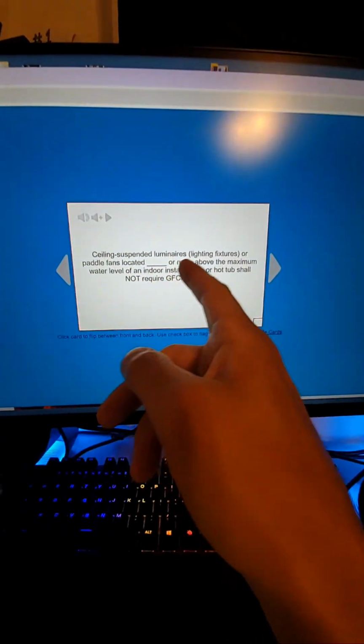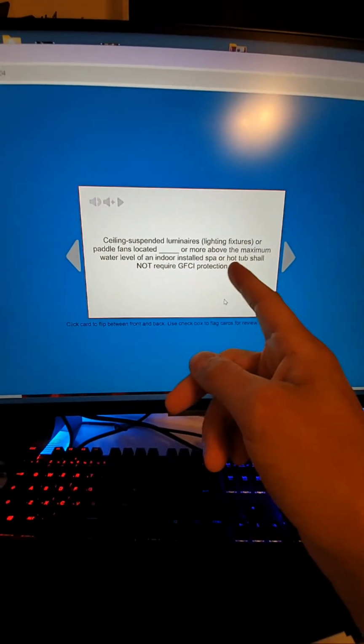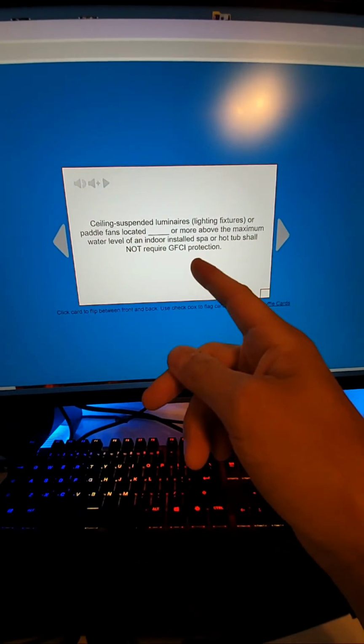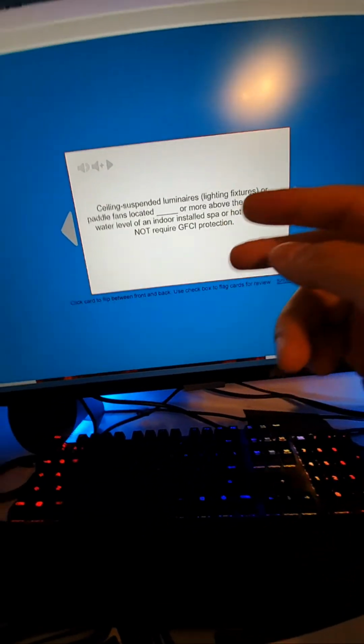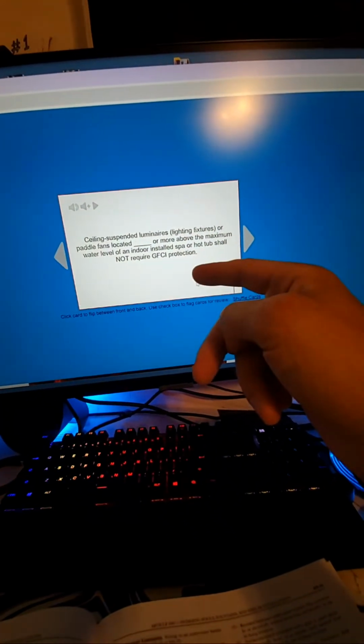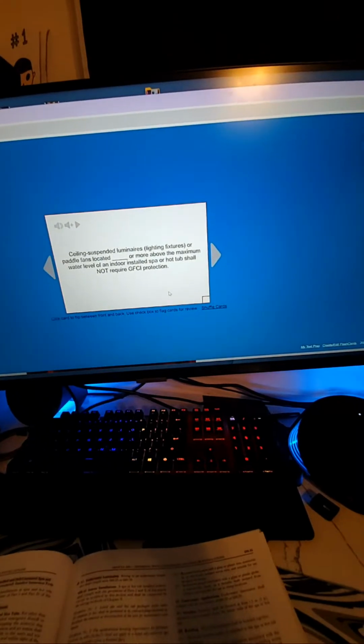Here's another one here. Ceiling suspended luminaires, lighting fixtures, or paddle fans located blank above the maximum water level of indoor installed spa or hot tub shall not require GFCI protection. Off the top of my head, I think that it's 12 feet, but we're going to look. So let's look at ceiling suspended paddle fans and the water level. I know that there's a water level part to this code. I'm just going to scroll through real quick. Here we go here. If we look at receptacles, so here is, this is overhead cables, pools, that's receptacles.